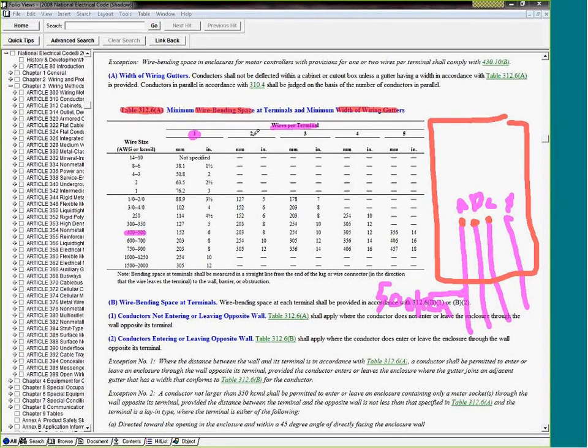Two wires per terminal, my friend Joe. This is your paralleling. If I want to parallel conductors, I put two wires per terminal. I'm paralleling. So the width that I need to pull the conductor in is at least 6 inches. The width I need is 6 inches, to pull these conductors in. It's big for them to move in. So that's basically the minimum. Again, this is just for the conductors. Doesn't include the material. So if conductors are coming in one area, you need at least 6-inch width.